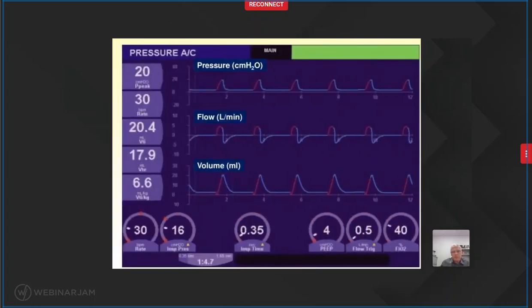So here's an example of a screenshot of a ventilator showing the three waveforms. On the top, you have pressure that usually is measured as centimeter water. In the middle, you have flow measured in liters per minute. And on the bottom, you have volume measured in mLs. And as you can see, most ventilators will display inspiration and expiration in different colors. In this case, inspiration is displayed in red, and expiration is displayed in blue. The important thing when you look at these waveforms is that you need to be sure that you're seeing the top and the bottom of each waveform. So you may need to adjust the scale to be sure that you're seeing the entire waveform on the three waveforms.